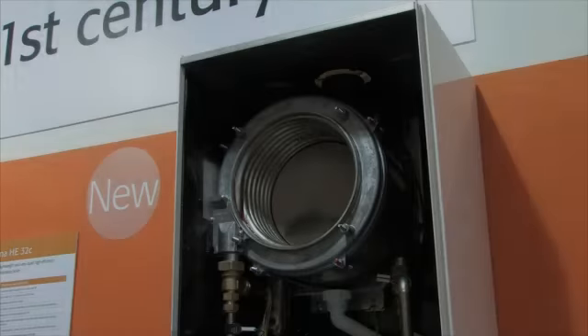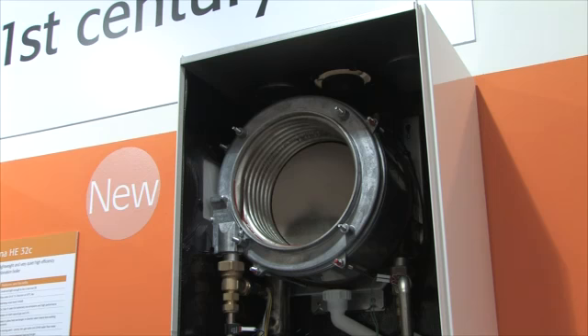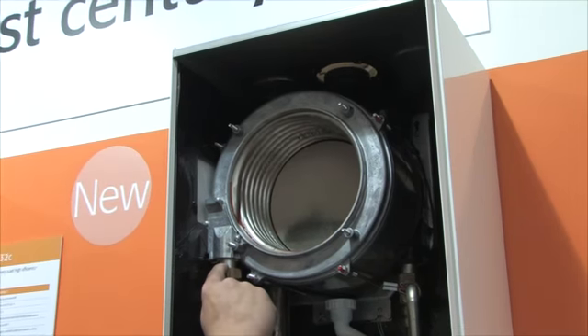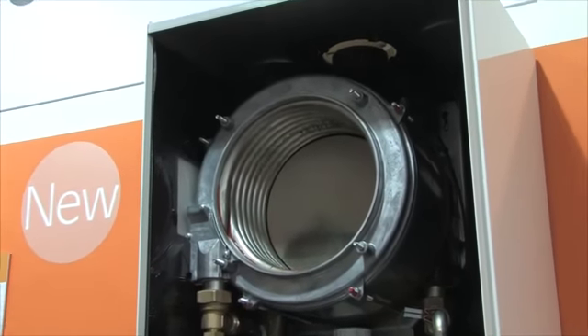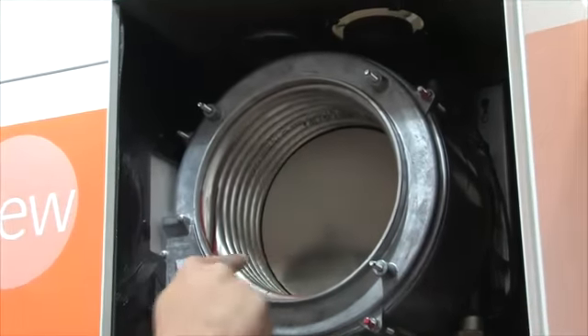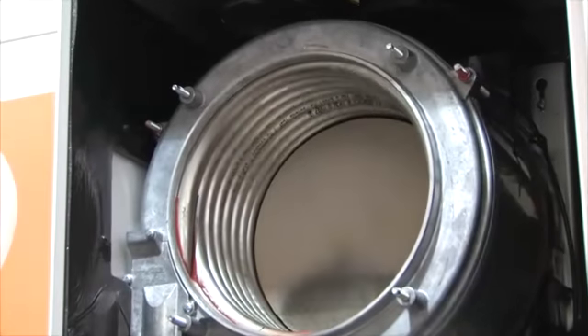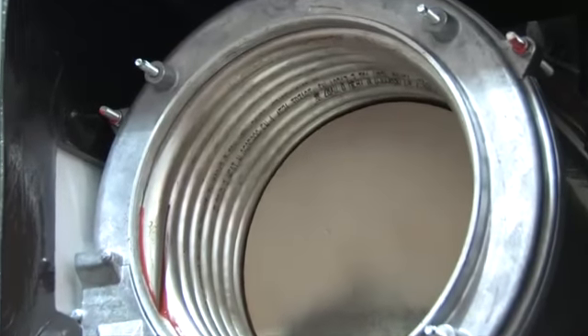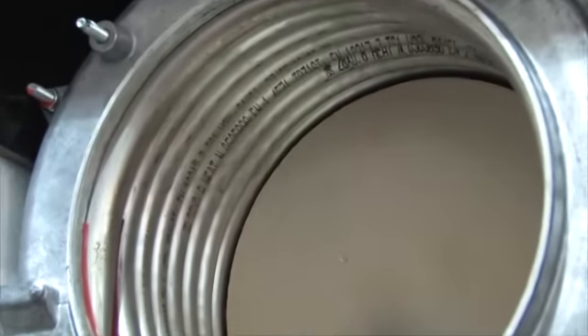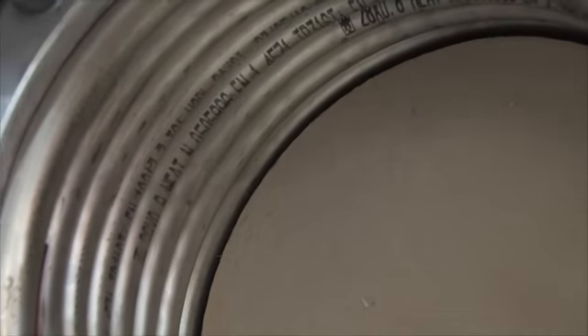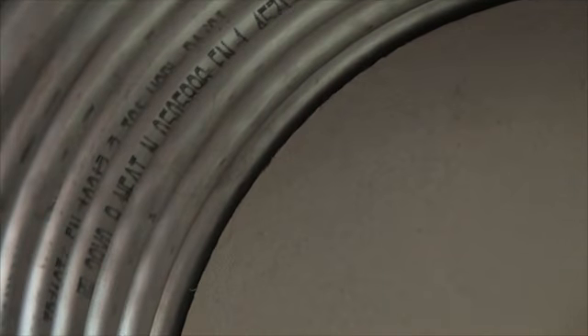Another superior feature of the Modena is the stainless steel bithermal heat exchanger, a great advantage over the traditional plate-to-plate system. This pipe-in-a-pipe system has a 12mm cold water pipe inside a 28mm compressed heating pipe. Both pipes are one continuous loop, which eliminates weak points and minimises potential failure of the heat exchanger. It also allows for efficient chemical flushing.